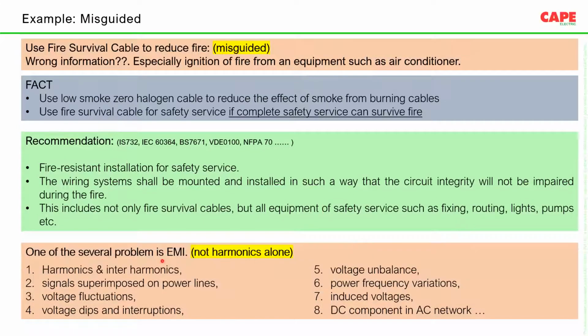The third one, a lot of places people say the third biggest problem is harmonics. So you make a harmonic study, and if you solve the complete harmonics, your full problems are gone. This is the third problem. But I will not put it as a harmonic problem. It's a power quality problem. It is EMI, including harmonics, interharmonics, signal dips, voltage unbalance, and there are so many issues which are happening. But doing only a harmonic study will not solve your problem. These things, I would say, are misguided.